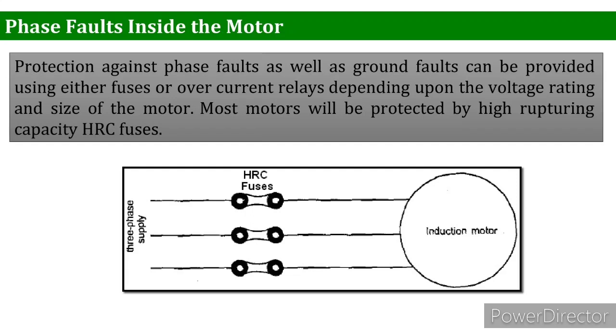Phase fault inside the motor. The protection against phase faults as well as ground faults can be provided using either fuses or overcurrent relays, depending upon the voltage rating and the size of the motor. Most of the motors will be protected by HRC fuses, and HRC fuses are basically high rupturing capacity fuses. And remember, we have studied the topic of fuses in detail, the basic working of HRC fuses and why they are used.